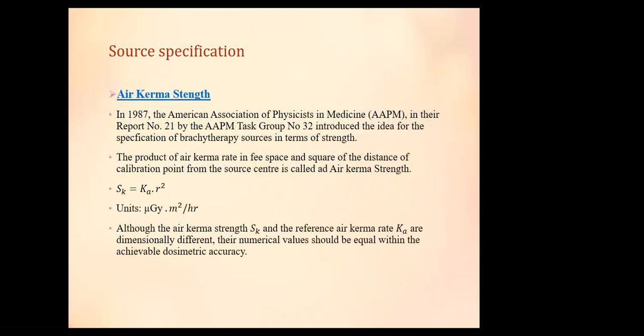And as for the air kerma strength, in 1987 the American Association of Physicists in Medicine, AAPM, in their report number 21 from Task Group 32, introduced the idea of specifying a brachytherapy source in terms of strength instead of exposure rate. The product of air kerma rate in free space and the square of the distance of the calibration point from the source center is called the air kerma strength.